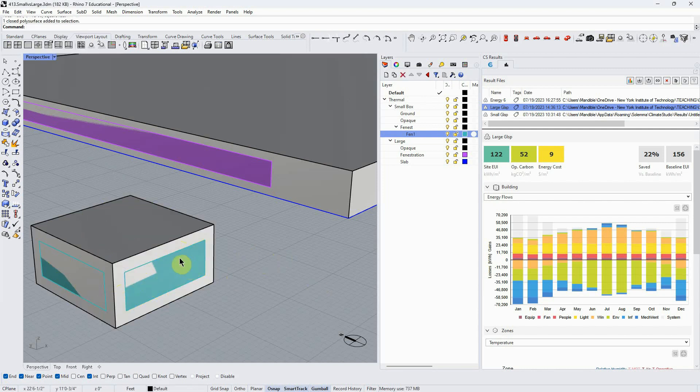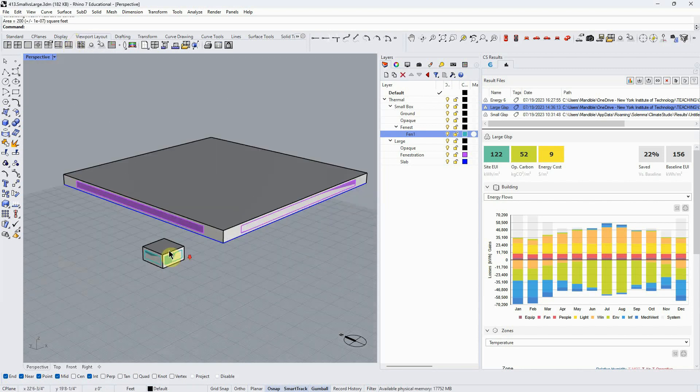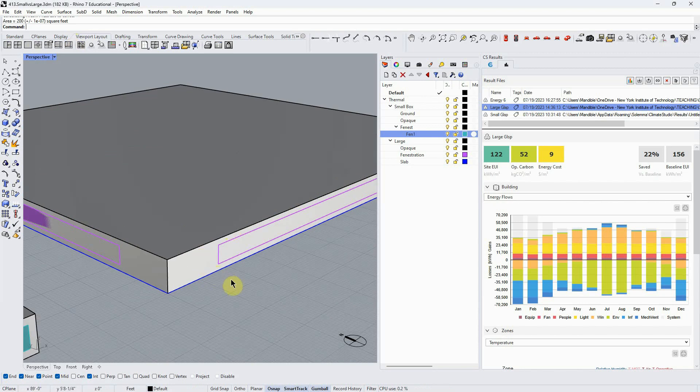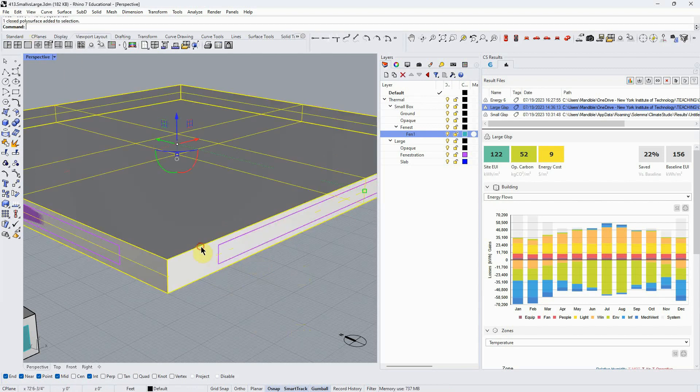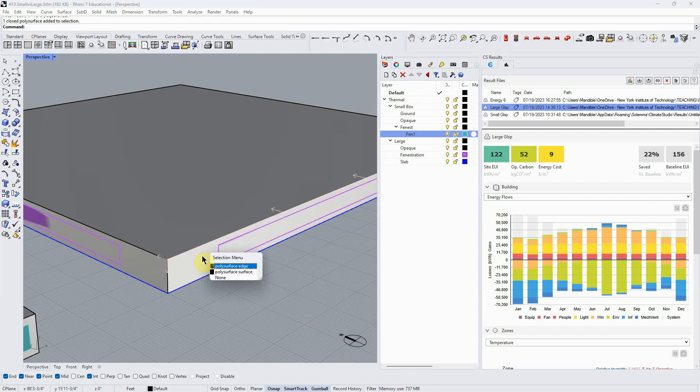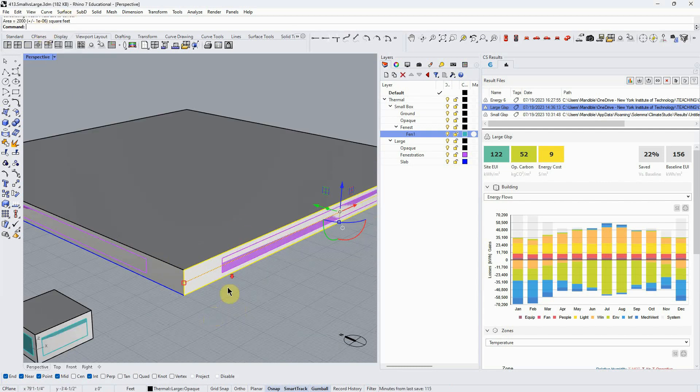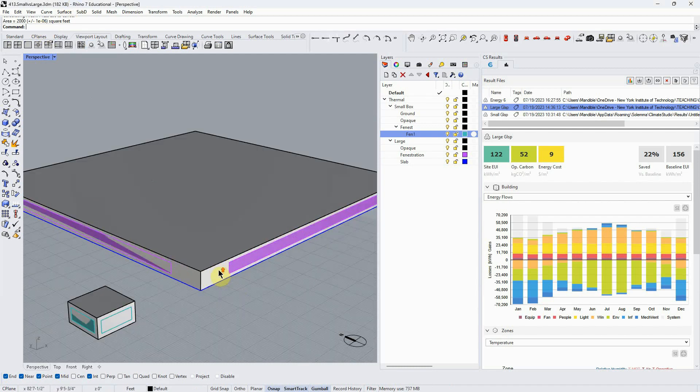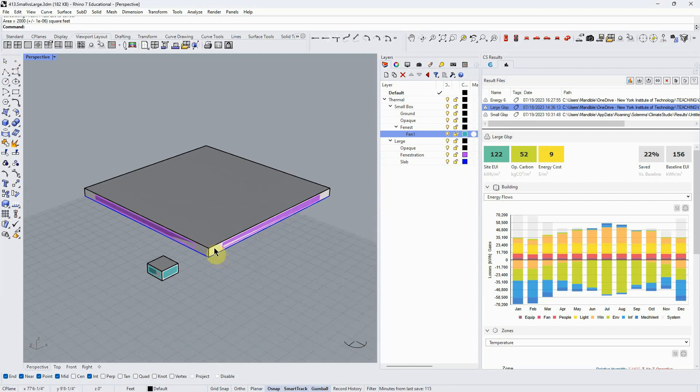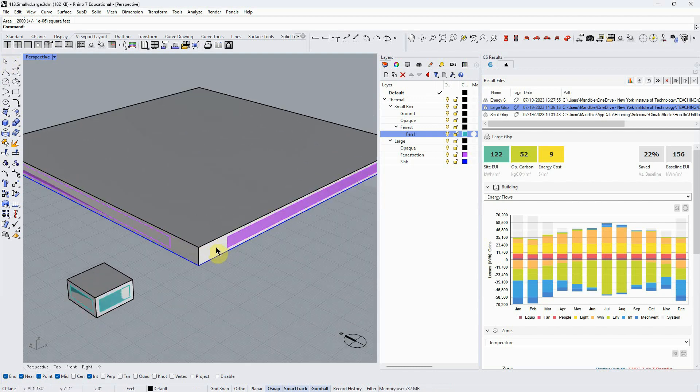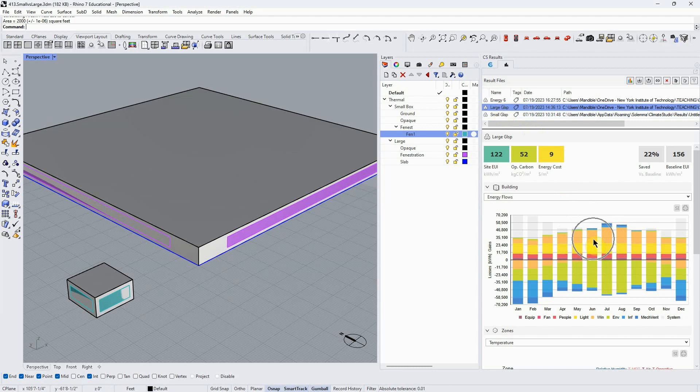While that is the same—let me show you that. This surface area is 96, and this surface here, the area is 200, so it's about two to one. If I come and do the same thing here, it's 960 and this one is 2000, so exactly the same ratio of window to wall. But we just have a lot more volume and square footage per square foot of exterior wall surface in this building than in this building. So that really drops the effect of the windows a huge amount.